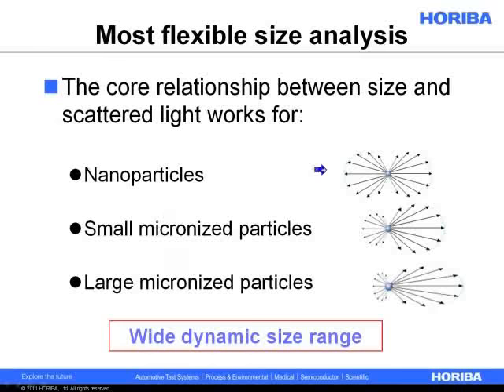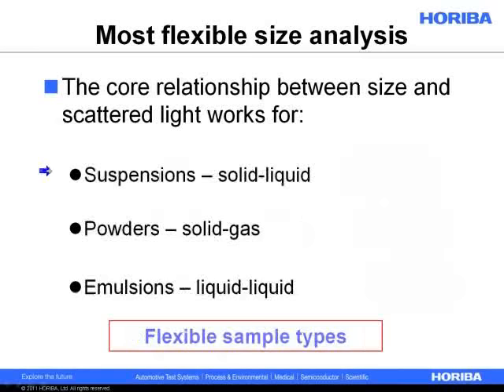It works for nanoparticles, small micronized particles, and large micronized particles. If a particle is small enough, the light will scatter essentially isotropically — this is also known as Rayleigh scattering. For a small micronized particle, most scattering will be in the forward low-angle regime. As the particle gets larger and larger, more and more of its light gets scattered in the forward low-angle direction. Diffraction is also flexible in the sense that it can measure many different types of materials — suspensions, powders, emulsions, and even creams and pastes using the right accessories.